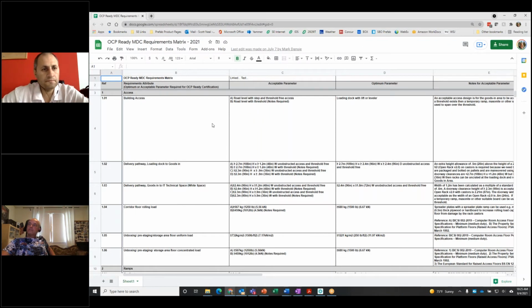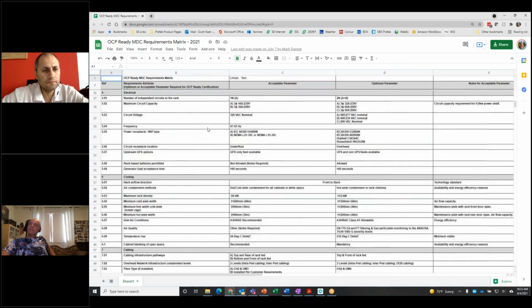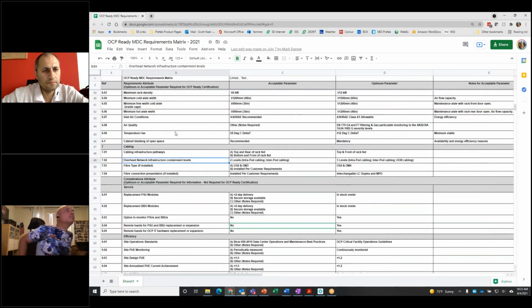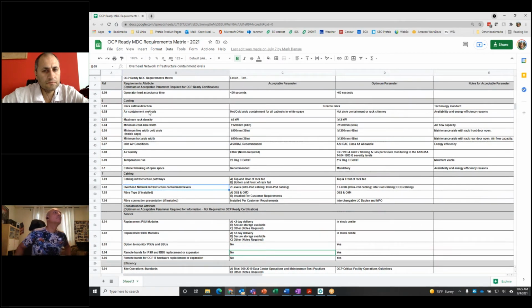This requirements matrix has a cooling section, right here. This is pretty basic - it's not getting into any technologies. It's basically saying, for an OCP rack, airflow is front to back. The acceptable parameter is some sort of containment, and the optimal parameter is hot aisle containment or chimney. I'd argue this is optimal, but that's a different discussion. Rack density is 8 kilowatts or 12 kilowatts, and there are aisle widths, so it's pretty basic.